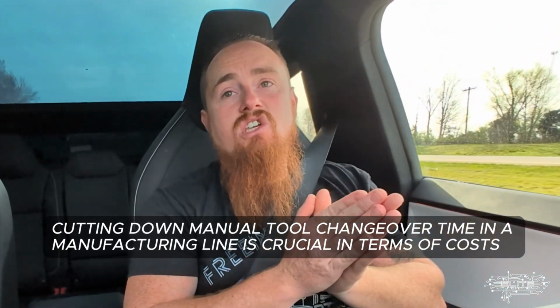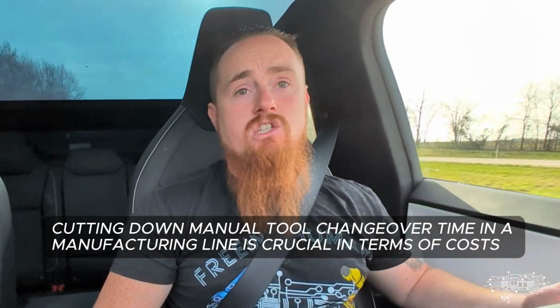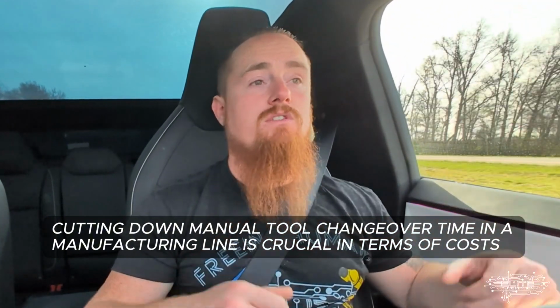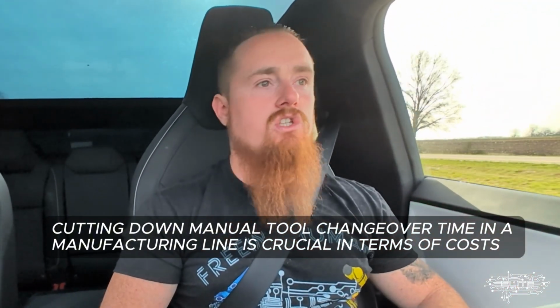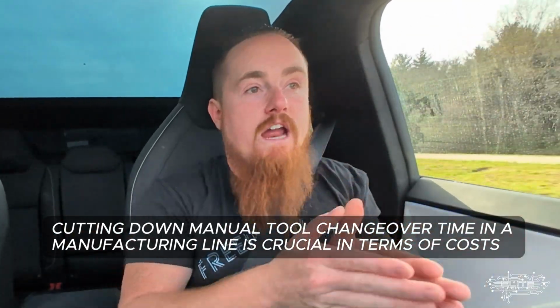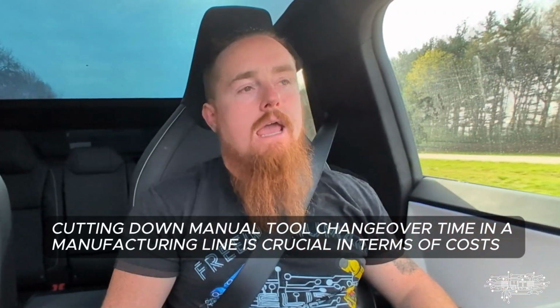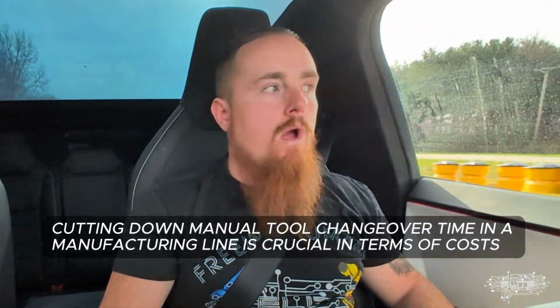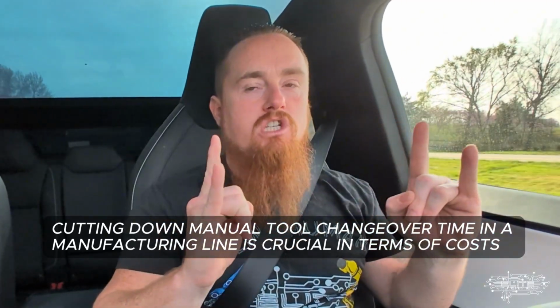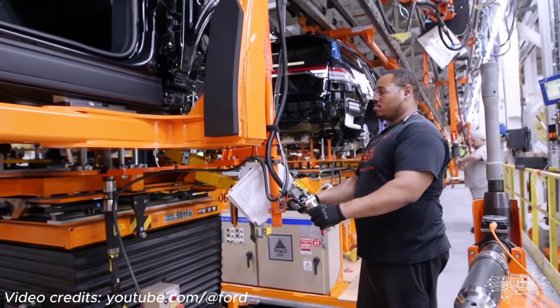Or you can have this system designed in a way that literally you can change over in like minutes. Like the overall mechanisms of the systems can change over in minutes. Maybe it's robots doing auto tool changing. Maybe it's conveyor track spacing able to separate because it's servo-driven and can change the conveyor width. Maybe it's your fixturing positions and those being on servos. And some things may still have to be manual, right?